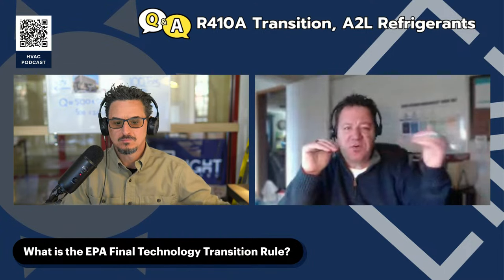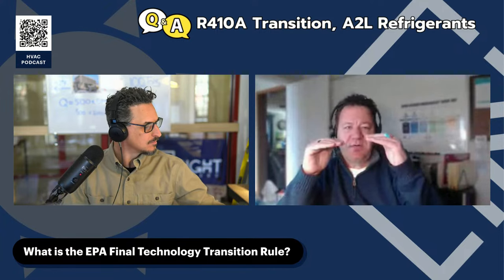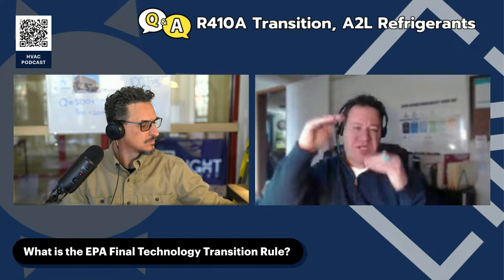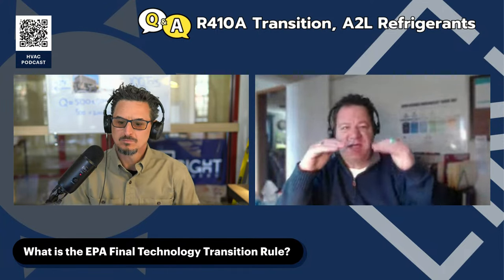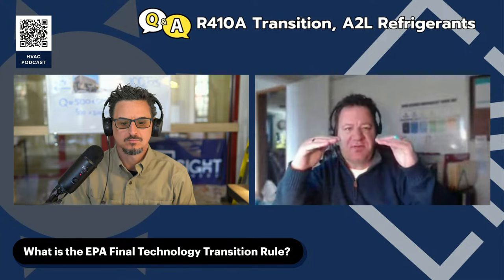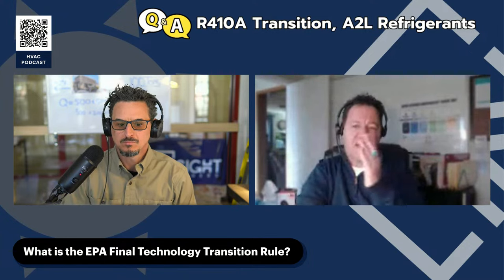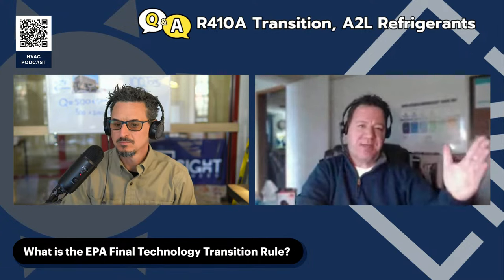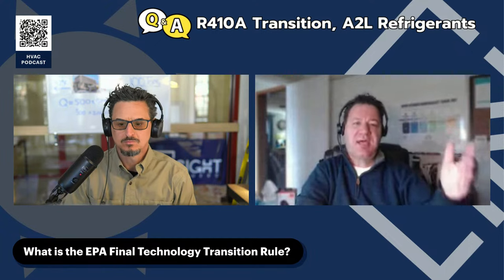Same components in those refrigerants. It's a 454 series, but the R32 and 1234YF ratio shifts. It may be a ratio of 80-20, it may be 50-50, it may be 60-40, but each one of those can fit a different application based on the pounds and the GWP.